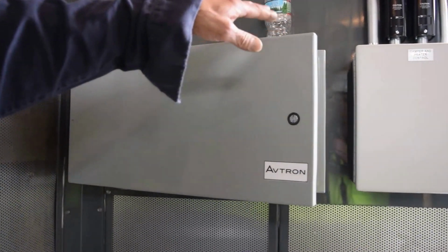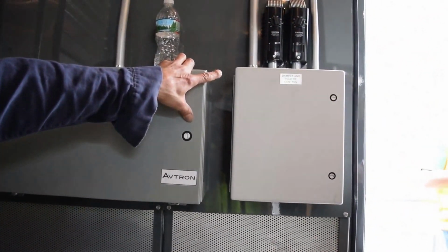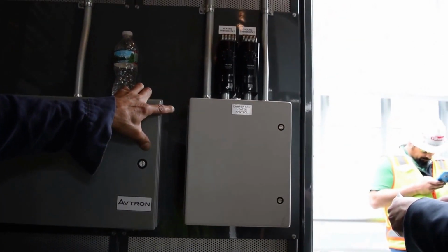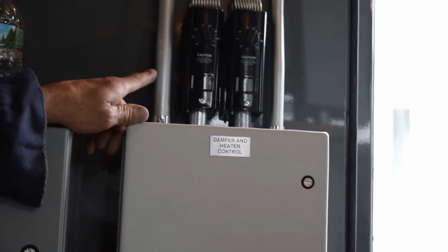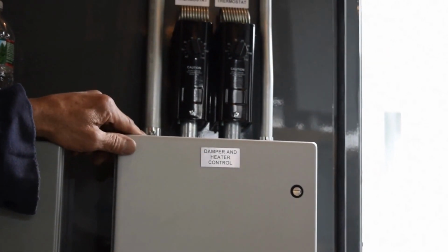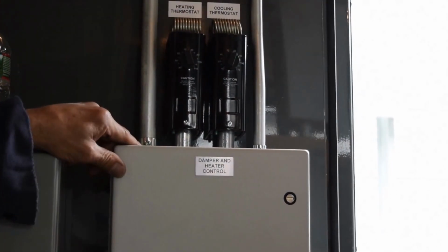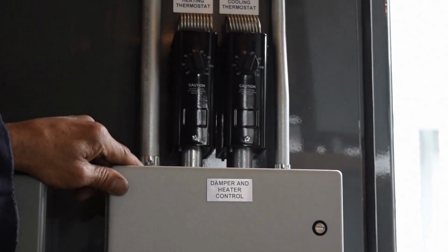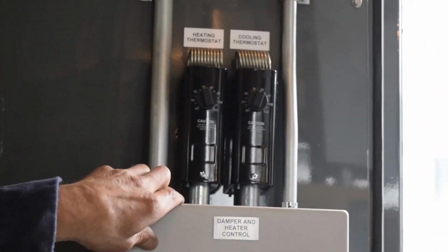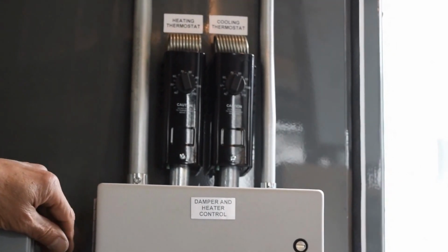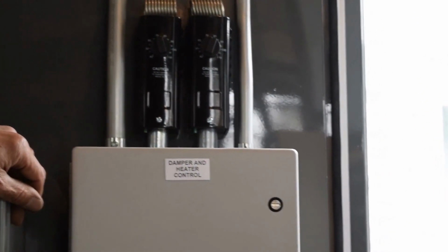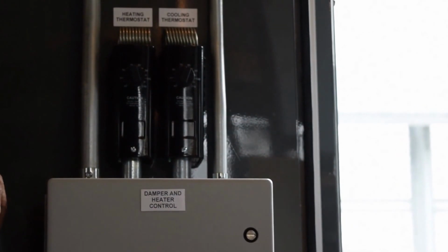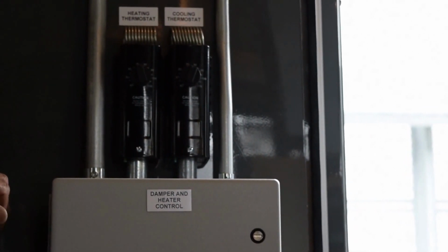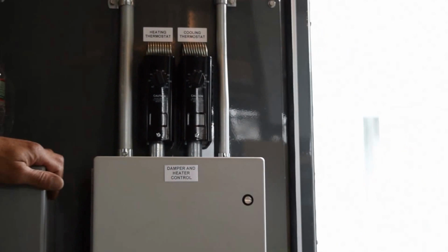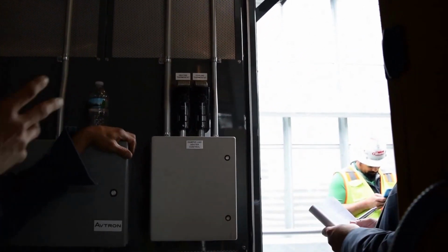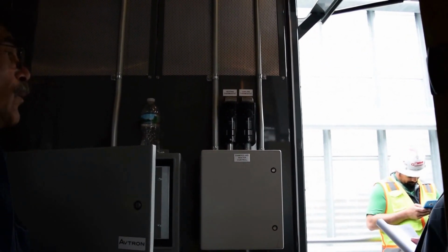We also have our heating and cooling controls over here. I should have noticed that before because that's the thermostat for the heater. The heater gets shut off when the generator's running. In the summertime, there's a cooling thermostat, and that will actually open the louvers and turn a fan on to ventilate the room, especially if it ran on a hot summer day for an outage or whatnot. It would automatically cool down to keep the room from getting way too hot, because now you have this big heat soak over here and everything's shut up and it was already hot to begin with.